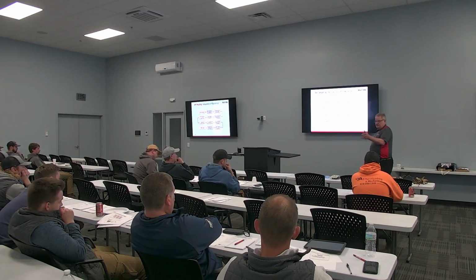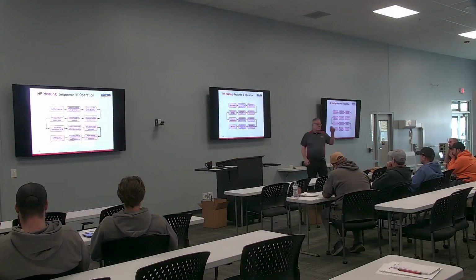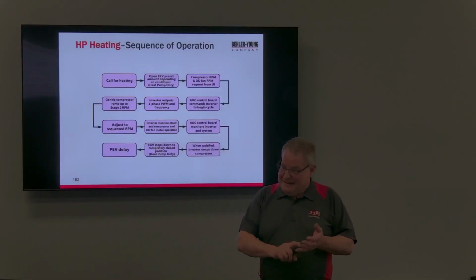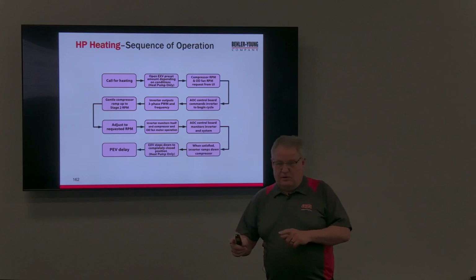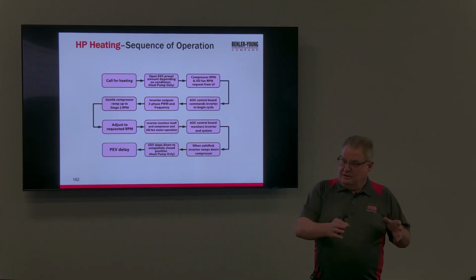It's bypassing, right? Remember, the flow is going backwards, so the TXV in the coil is bypassing. Now, one of the things when Dave was talking about airflow, when you're dealing with heat pumps, and I know in Michigan, 10, 15 years ago, we didn't put many heat pumps in, right? They didn't work. They do now. So don't forget when you're dealing with your indoor airflow on the heating stage, that's your condenser fan. So it's just as important when your heat pumps are running, because that is your condenser fan.